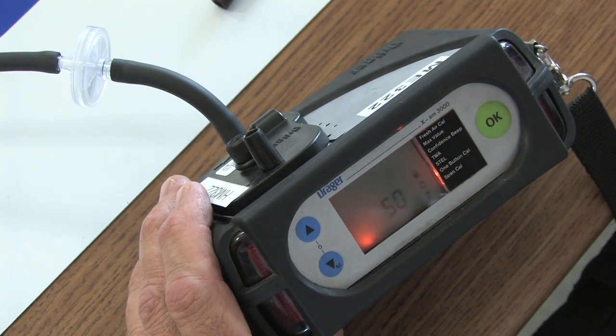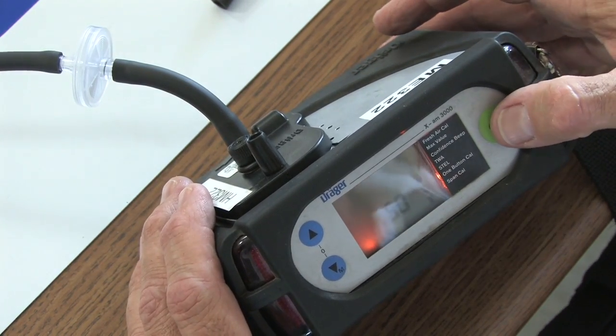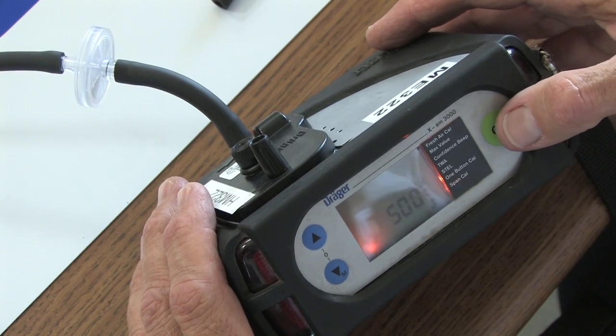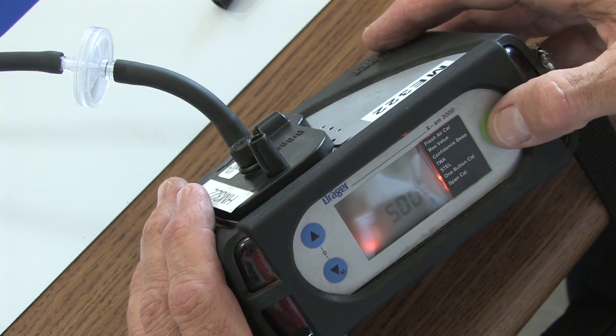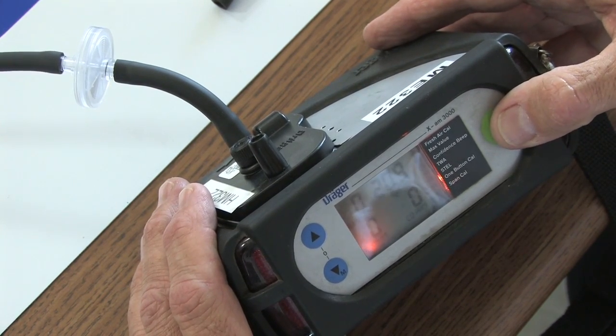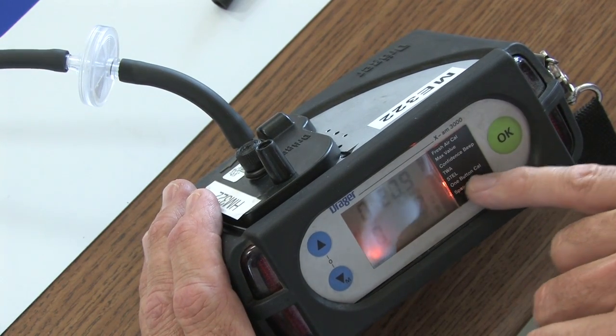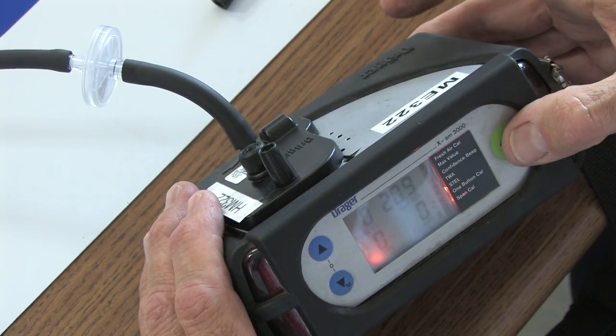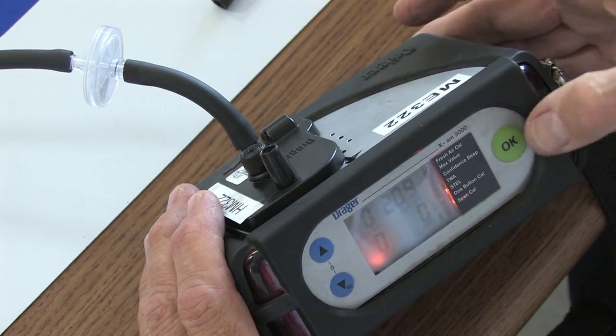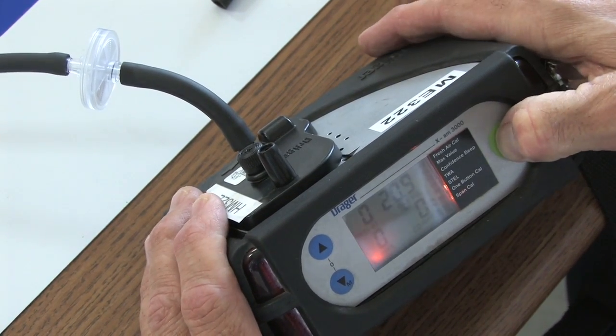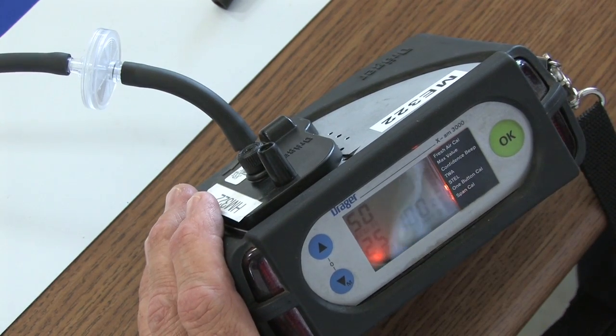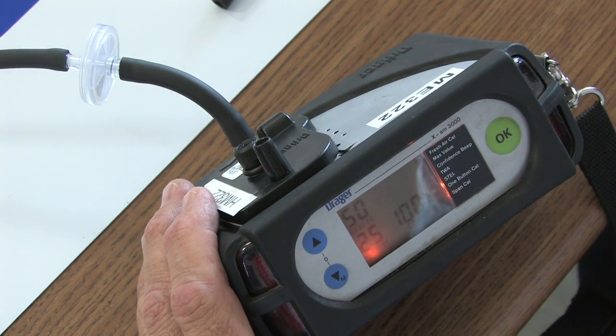So that kind of operation is somewhat similar to the single gas PAC 7000 in the way it operates. Then I hit it again. And then the arrow is now hitting one button cal on my exterior sticker. I'm going to go ahead and hit OK twice, maybe 3 times. There we go. You saw it took me 3 times to get it to move.